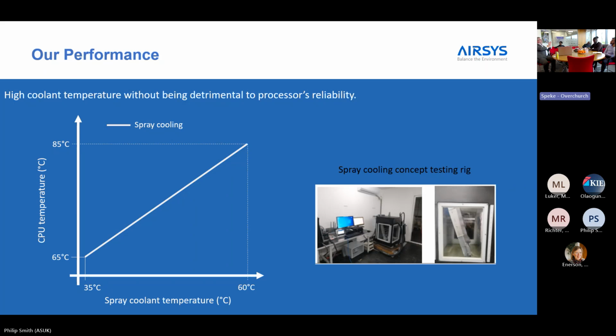Ours, basically, is inclined at about a 30-degree angle, and it's sprayed and it runs down. So you're only really spraying the bit that's hot. You can then turn off that sprayer for that one particular server, extract it so that it's proud of the drawer. It'll run off in 10 minutes. Then you can remove it, do what you need to, put another one in. The other 6 in the drawer are still cooling. You don't lose cooling to the other 6 by taking one out. It still carries on. So it's a very novel solution.